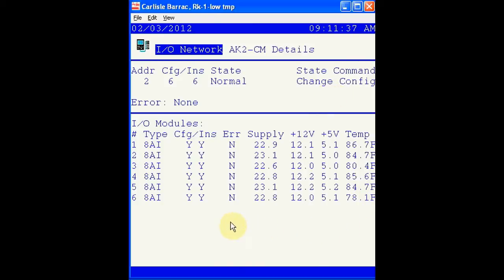Here you see important information about each board, including the type of board, whether it's configured in the 255, whether the 255 can see that it's installed, and any problems on the board. The supply voltage refers to the voltage used to power the COM module, and can vary from the actual voltage. This column shows us that the regulated 12-volt supply is a good voltage level. In similar fashion, the 5-volt supply is listed here. This temperature is a temperature recorded from the board itself, based on a small thermocouple incorporated into the board. It will commonly run slightly higher than ambient temperatures. All indications are that communication module number 2 is working correctly.